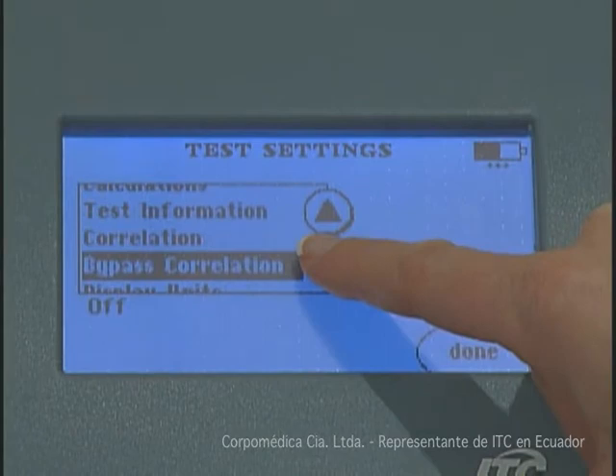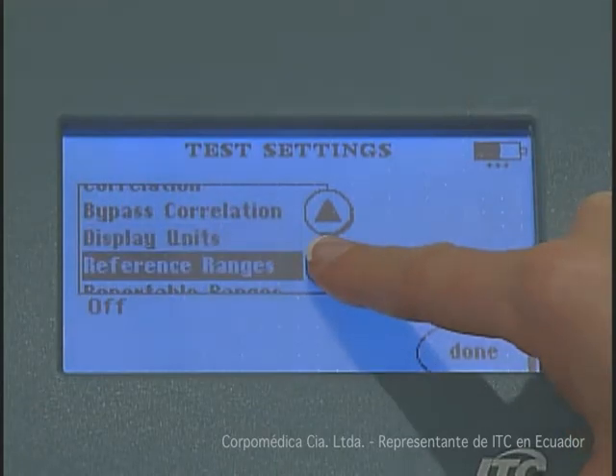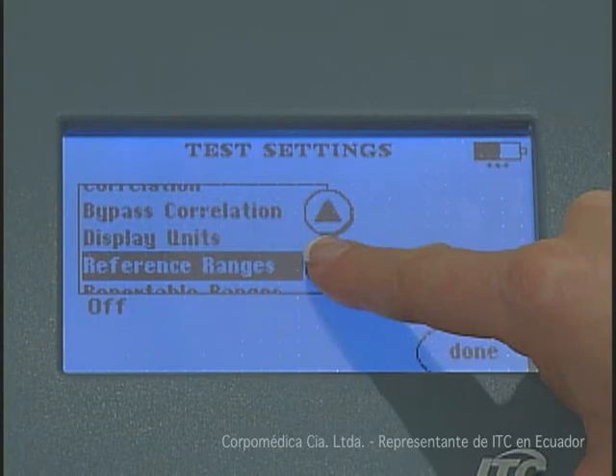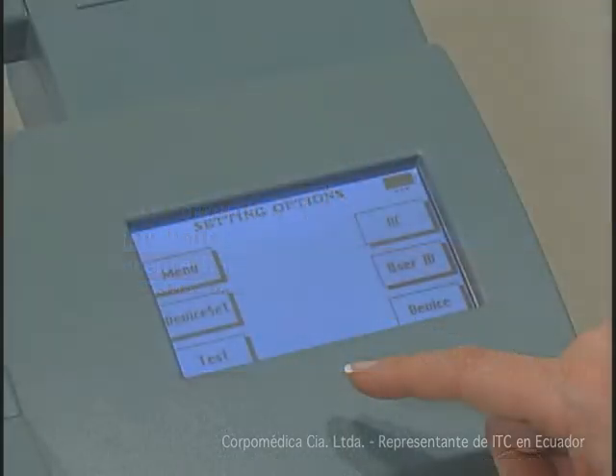The IRMA TruPoint has a bypass correlation feature that can be activated during times of hemodilution, which is commonly experienced during cardiopulmonary bypass. See the user's manual for reference and contact ITC technical support for assistance. The reference ranges can be established for various patient types. Out-of-range patient test results can be flagged as high or low. Product setup defines the cartridge types to be used in the facility or which analytes are reported.